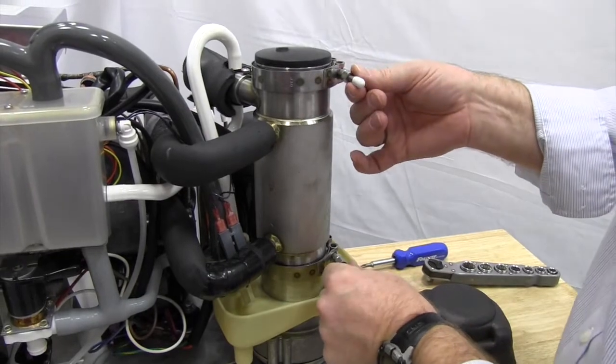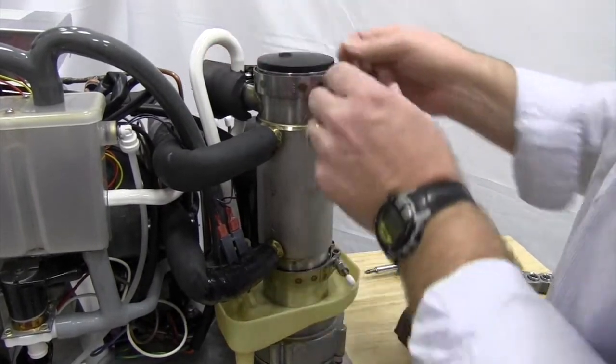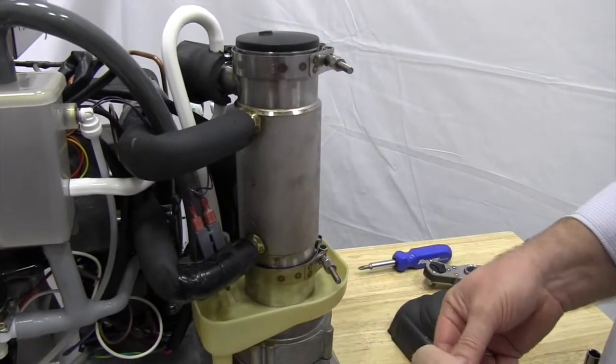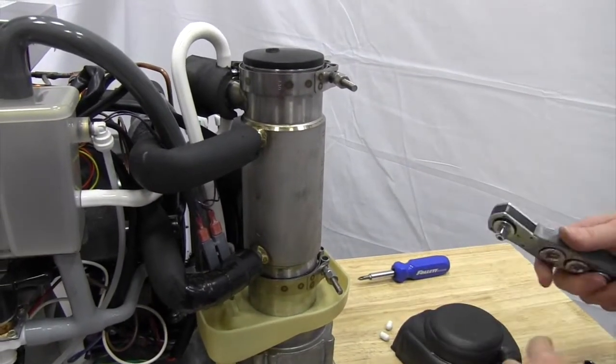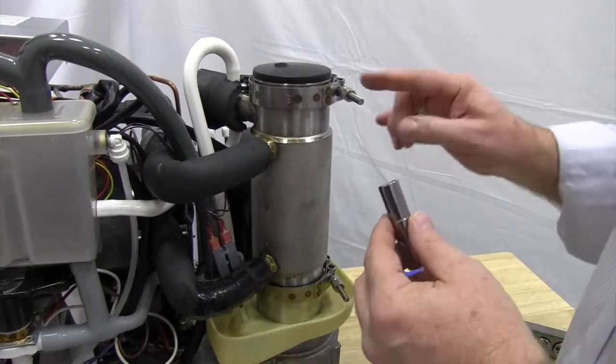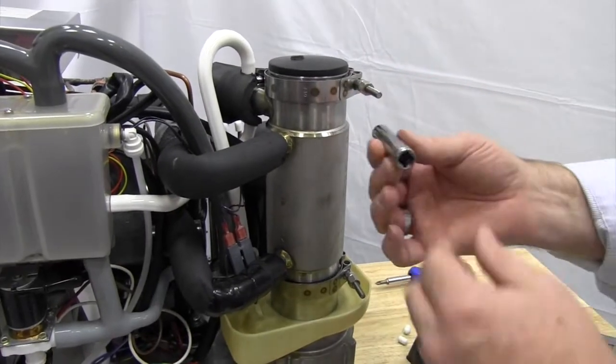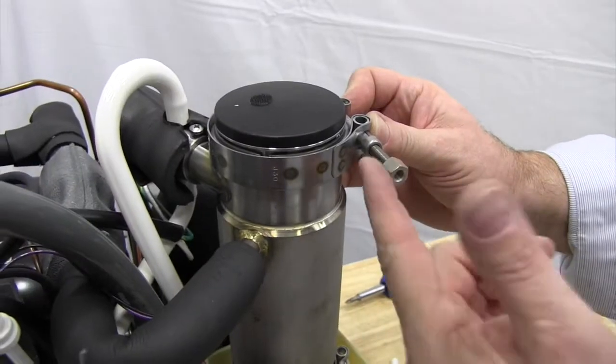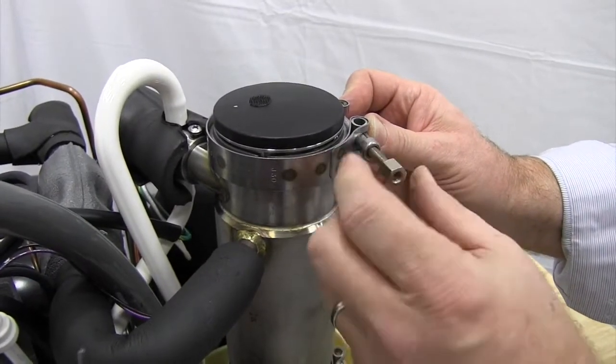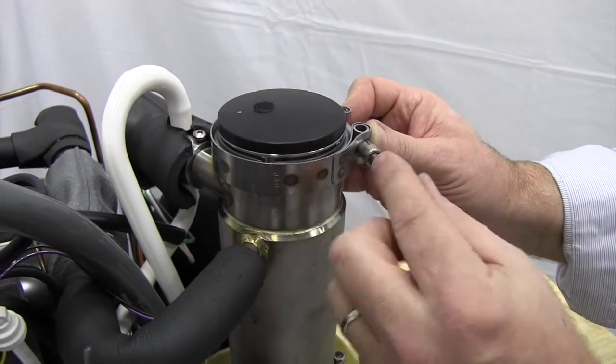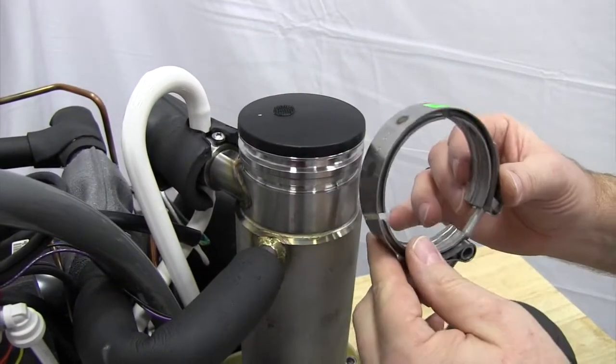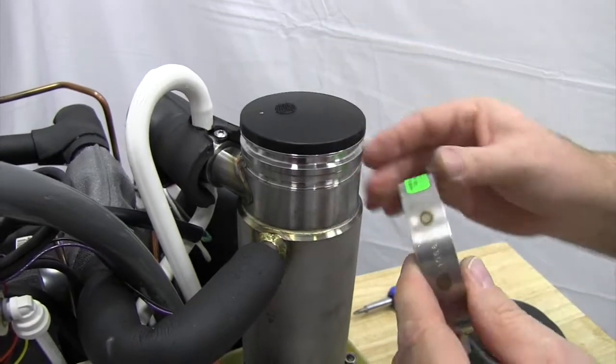And we expose our V-band clamps. We've got a couple little protective caps over the ends, and we're going to take these nuts off with a deep well 7/16ths socket. I've loosened up my V-band clamp. You want to take the screw almost all the way off, spread the V-band clamp off, and take it off the top of the upper bearing.